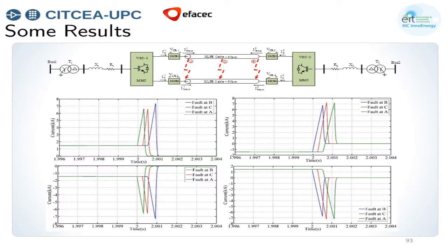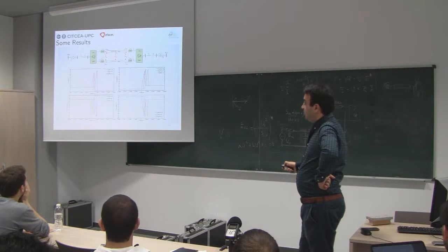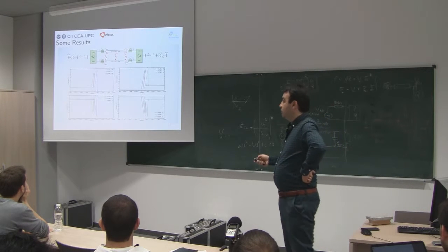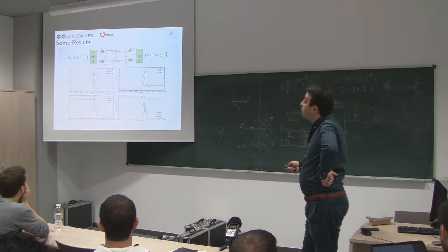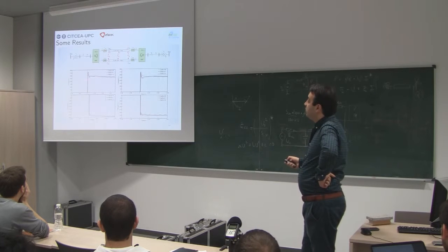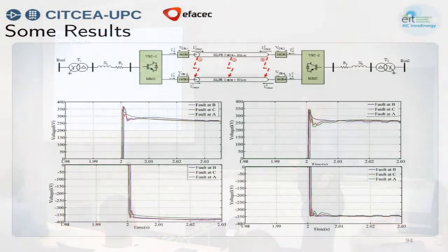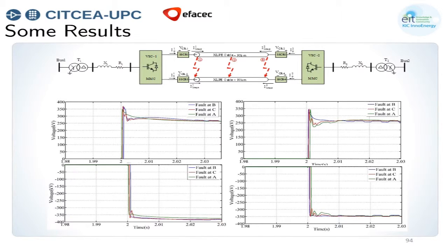So if I want to show you the current flowing from each converter, from the positive pole and the negative pole, you can see that after introducing the fault, we can interrupt the fault current very, very fast from the converter. So the converter will not be under so much high pressure. So we have the voltage across each breaker here. You can see it's quite in an acceptable range. For 320 kV, we have something like 30 kV of transient voltage, which is quite normal, and we can have even more than that.